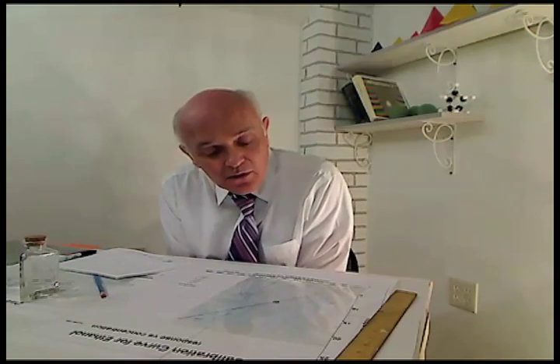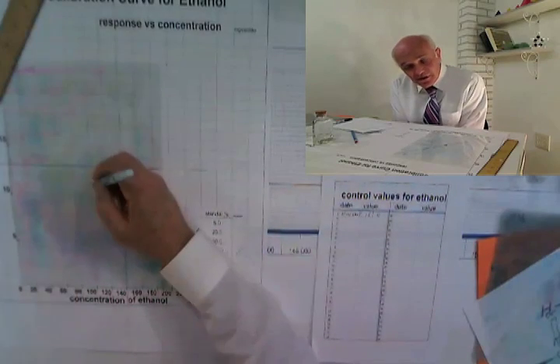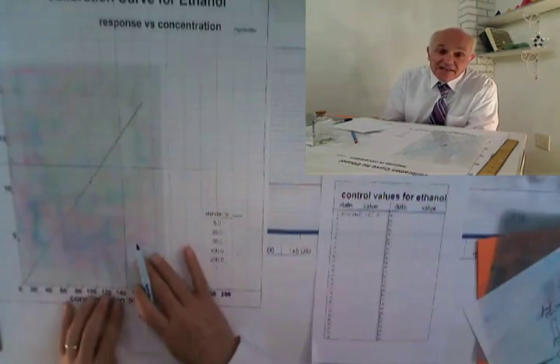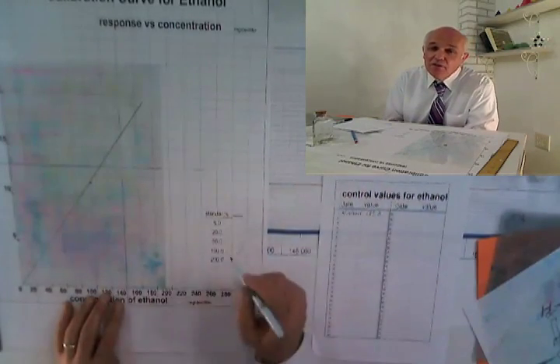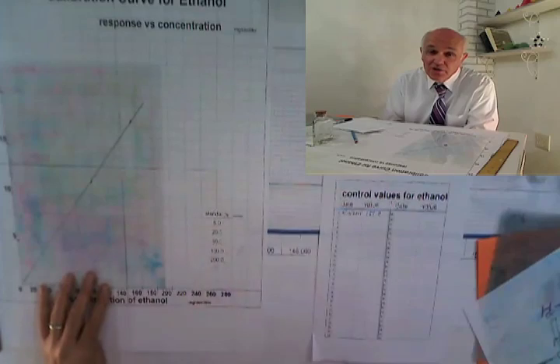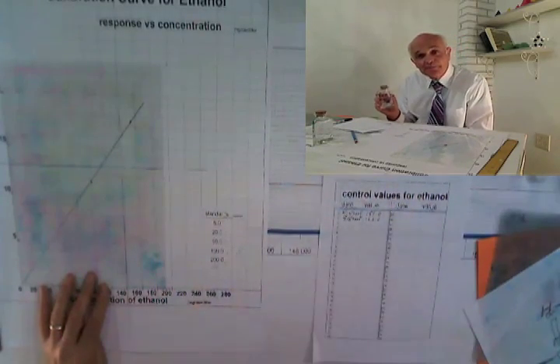But how do we know this is true? You can't really see ethanol — it isn't like getting on a scale. You've sort of taken it on faith that 10 microliters into this instrument will give a linear response. The way we establish this to a very high degree of certainty is we use an external control sample.